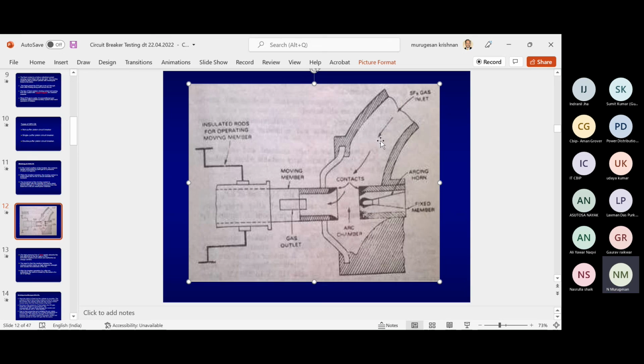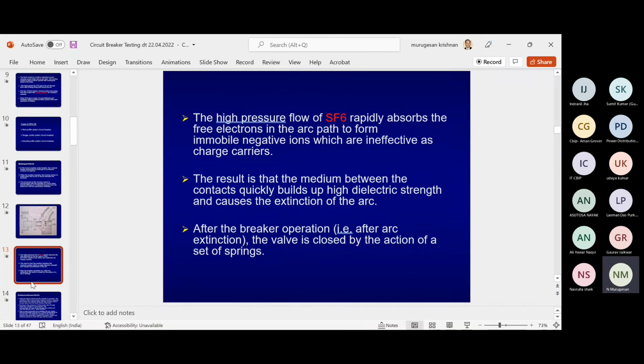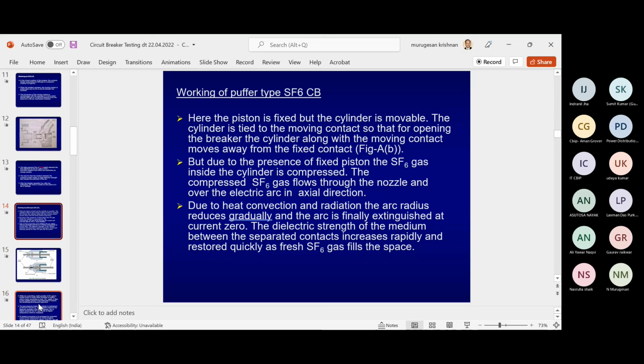So when it opens, the gas comes into the picture, the arc chamber opens, and this SF6 enters, increasing the resistance, so the arc gets quenched. You can have a look at this. These are different types of puffer type SF6 breakers. Here the piston is fixed and the cylinder is movable. Due to the fixed position of the piston, the SF6 gas inside the cylinder is compressed. The compressed SF6 gas flows through the nozzle and over the electric arc in the axial direction. Due to heat convection and radiation, the arc radius reduces gradually, and the arc is finally extinguished at current zero.